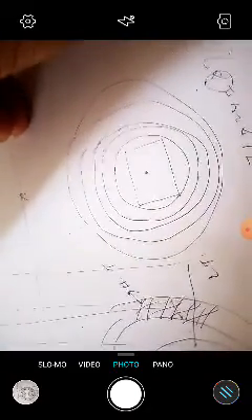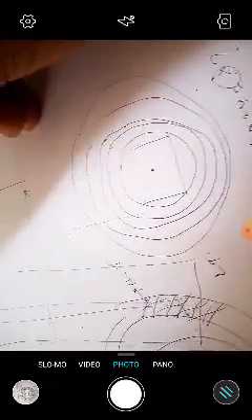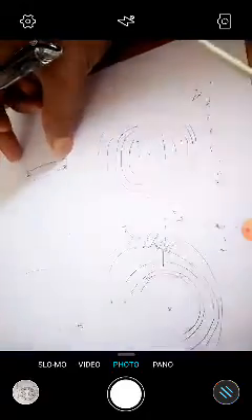Now after extending these, take one base and, from a certain point, as you have seen in AutoCAD, take the height of the LT winding, that is the total winding cut. One more most important thing: make sure the center of the yoke is calculated. The height of the yoke will be decided at the center of the core. This is the height of the winding, a complete total box of the winding, but these two center points will give you the height of the yoke.